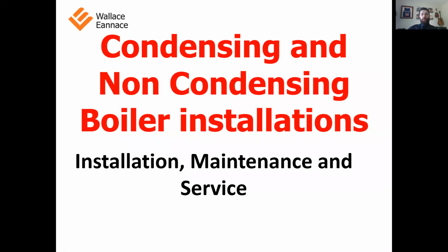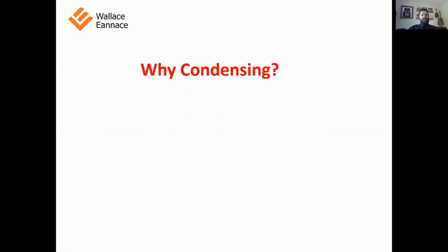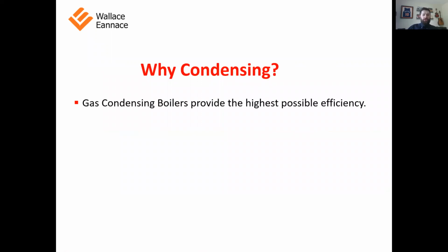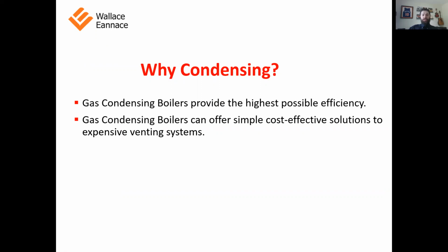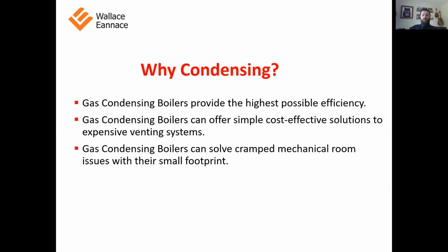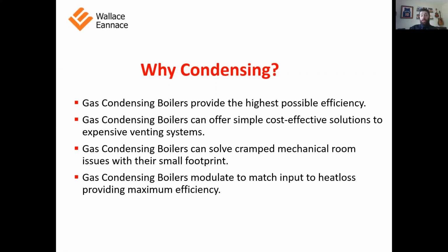So today we are going to talk about condensing and non-condensing boiler installations, maintenance, service, go over a little bit of that. So first, why condensing technology versus non-condensing? Gas condensing boilers provide the highest efficiency possible. They also are cost-effective venting systems. They can solve cramped mechanical rooms, small footprint. A lot of them are low mass when you compare them to the old style non-condensing copper heat exchanger models, which can be much bigger, especially on the floor. A lot of them lay horizontally.